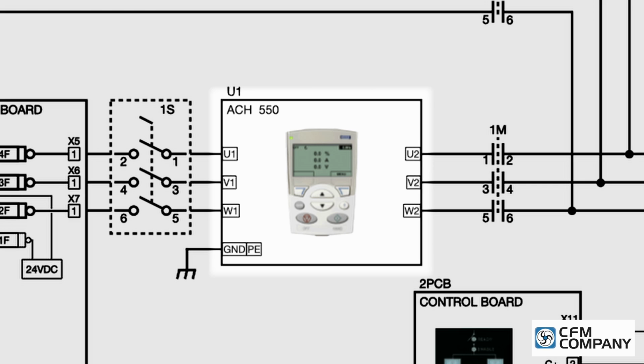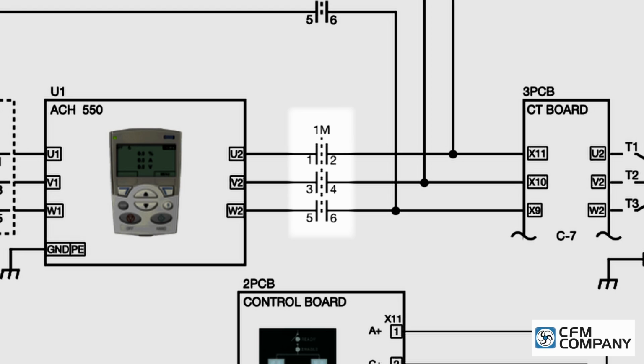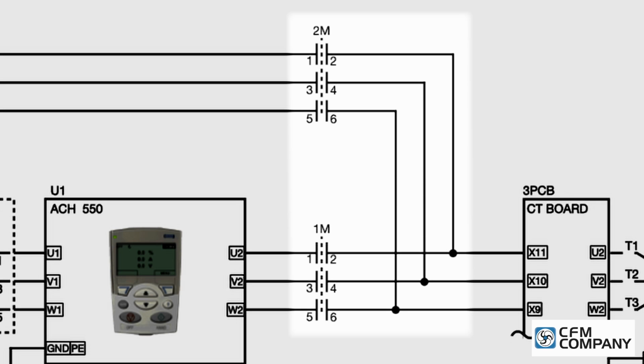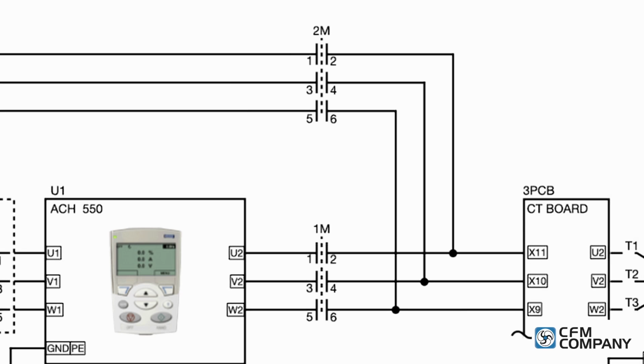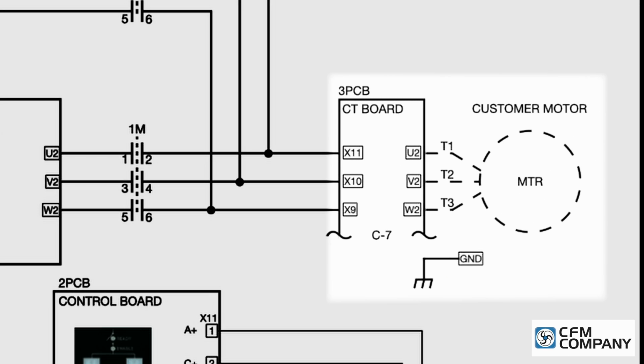The drive output terminals U2, V2, and W2 are connected to the line side of the drive contactor, 1M. The output of the bypass contactor, 2M, is wired in parallel to the output of the drive contactor, 1M. The output of the bypass and drive contactors is wired to the motor terminals on the CT board.